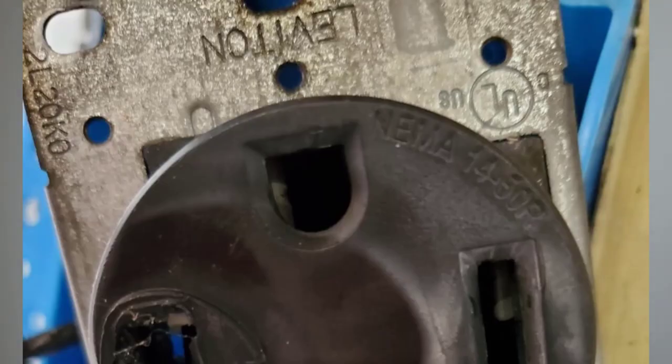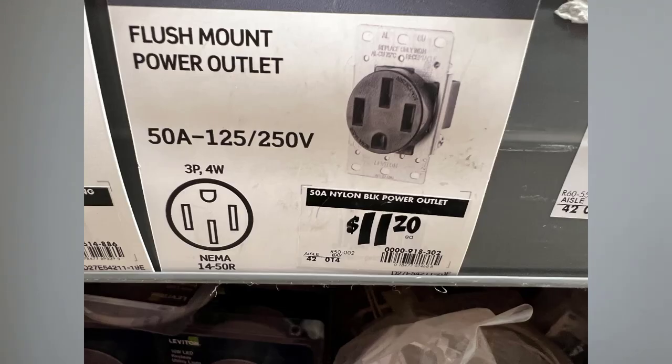This distinction appears to be somewhat arbitrary, and Underwriter's Laboratory does not seem to make a formal differentiation. From what I have been able to determine, the Leviton outlet, which is found at Home Depot or online for under $15, and was what this owner used, seems to be the light duty version.